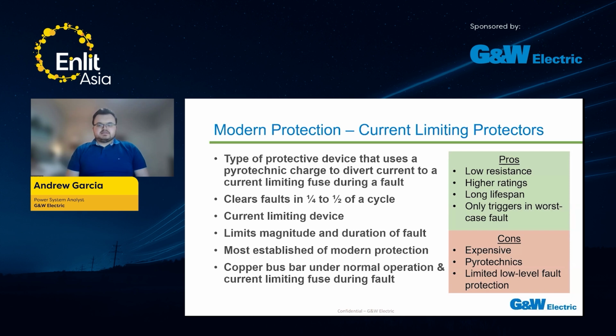So once again, as with all modern technology, these are expensive. The pyrotechnics may be something that people are wary to use. They might feel it's unsafe, that it introduces a new hazard to your system. I will say though that with these devices, those pyrotechnics are completely contained when the clip or current limiting protector triggers, so there's no additional hazard to your workers. And as a result of how this works, because it's only designed to trigger in the worst case fault scenarios, it's going to have very limited low-level fault protection. So if you have a small fault on your system, your regular system will have to handle it, your other devices, and this will not trigger.